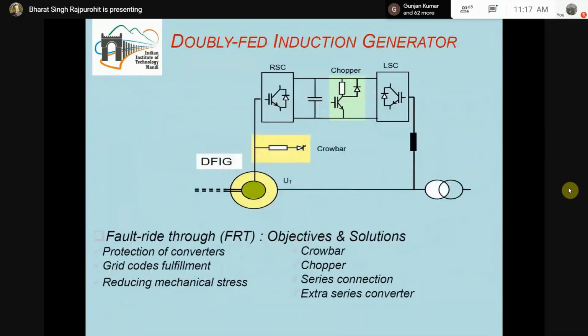But during this time, if the squirrel cage induction generator is there due to the crowbar operation, who is going to provide the reactive power support? Because the rotor side converter is not connected. So during this time, the line side converter can act as a static compensator and will be able to feed the required reactive power for the operation of the DFIG as well as the grid requirement.